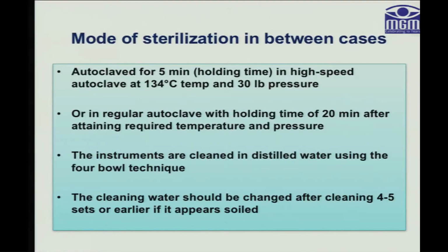For sterilization in between cases, autoclave can be done for 5 minutes holding time in a high-speed autoclave at 134 degrees temperature and 30 pounds pressure, or in a regular autoclave with a holding time of 20 minutes after attaining the required temperature and pressure. The instruments are cleaned in distilled water using the 4-bowl technique. The cleaning water should be changed after cleaning 4 to 5 sets, or earlier if it appears soiled.